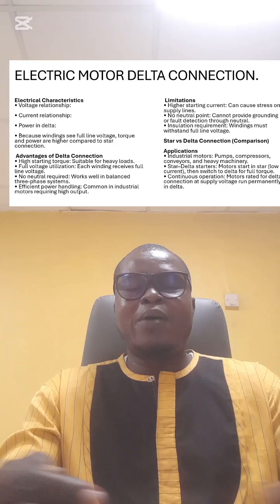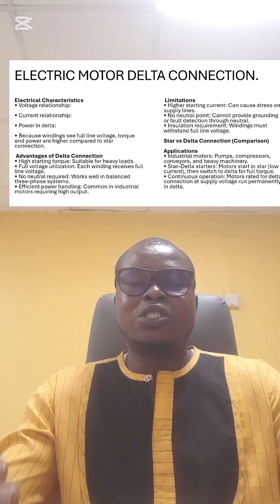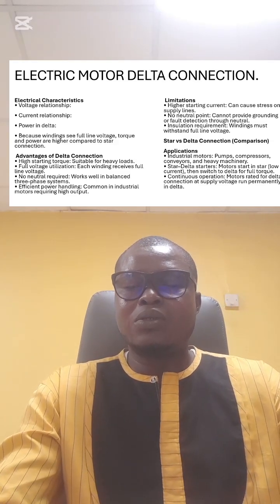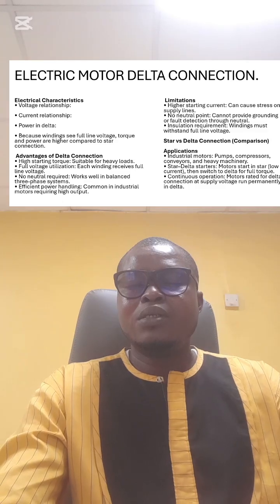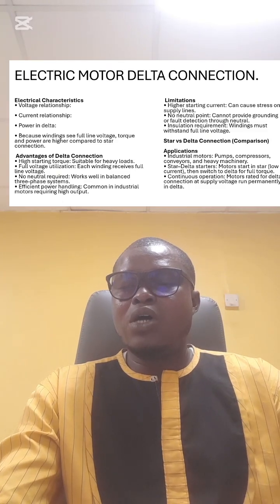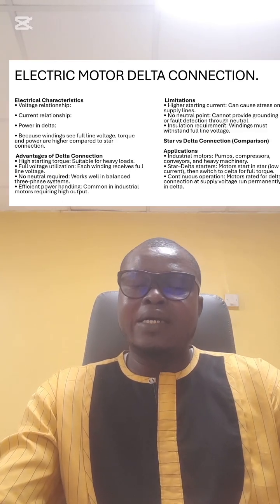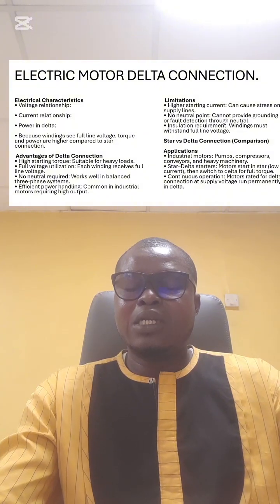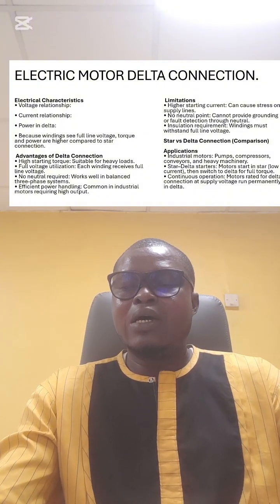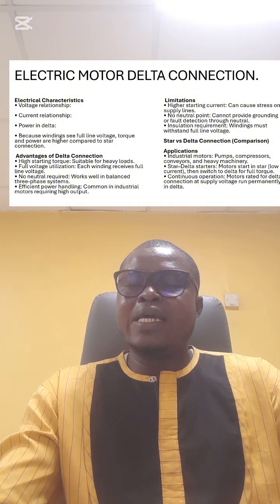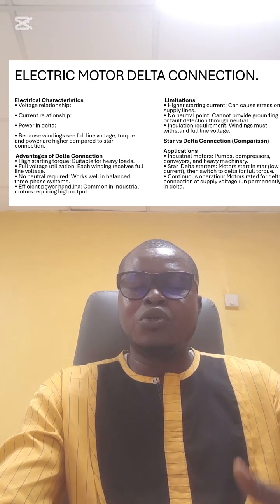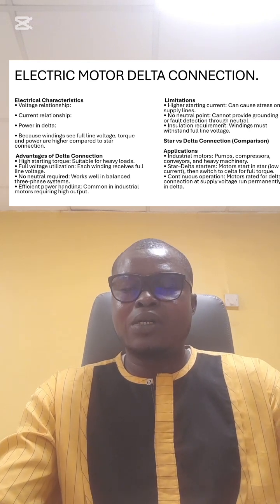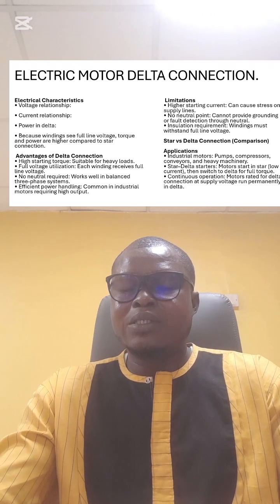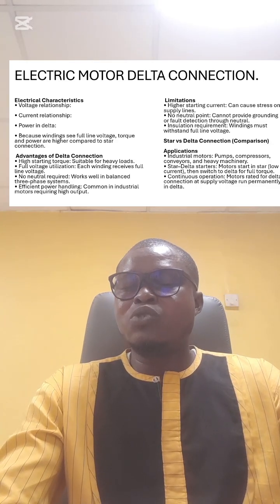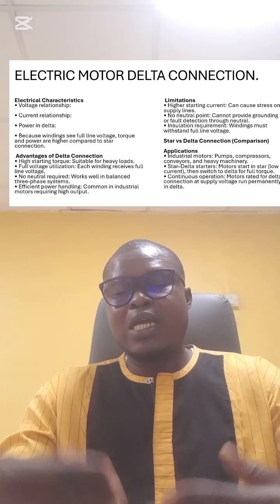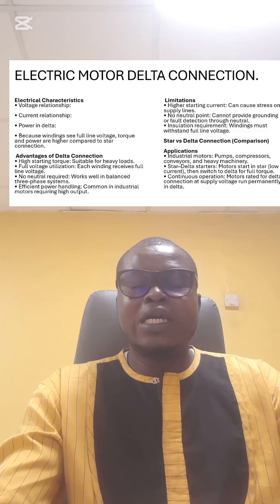Now, we can talk about the advantages, but there are also limitations to this delta connection. The higher starting current can cause stress on the supply line, which is a limitation. There is no neutral point, which means it cannot provide grounding or fault detection through the neutral, which is also a limitation. Then an insulation requirement, which means that the winding must withstand a full voltage because it is a high voltage, is also a limitation.